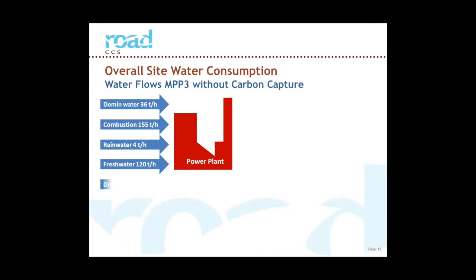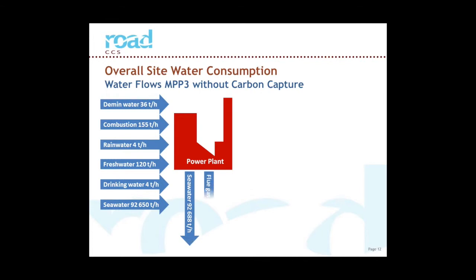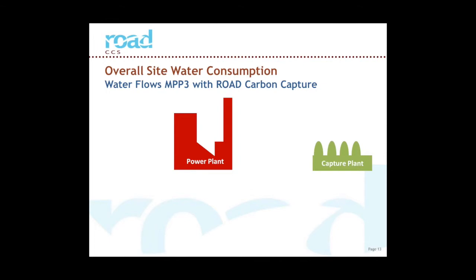So then the water coming out, the seawater, now we've increased the seawater supply coming out, and that's because a lot of the waste streams are treated to a quality where they can be discharged into the sea. So some of the demin water and other water sources end up in the seawater. The flue gas, you can see a big increase in the water in the flue gas from the water in combustion, and that's because of the quenching effect of the FGD. Adding water, and there's a few other minor losses. This is either water that escapes as steam or wastes that are not of a quality that they can go into the seawater. So that's the main power plant, and that's the reference point. Now we can talk through the impact in terms of the water balance of adding the capture plant.